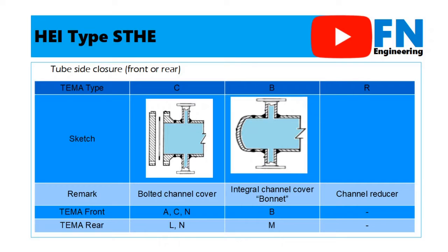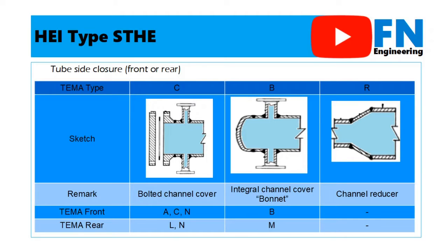The next type is type B. Type B is an integral channel cover or bonnet head. It is like type B in the TEMA standard in the front head or type M in the rear head. The last type is type R, or channel using reducer. This type is not identified in the TEMA standard.